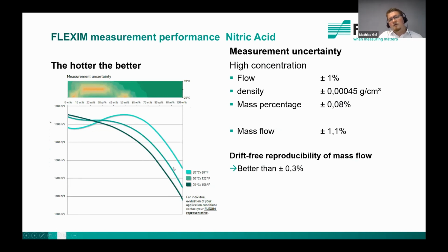And we use this together with a temperature measurement, which can also be done clamp on, or we can integrate the temperature measure you have on site. And then we can calculate the concentration, the density, the mass flow, the mole weight, whatever is required on your end. And for those of you who have asked questions about how accurate this can be, if we're talking about flow, we're always around ±1% in volumetric flow here. And then when it comes to the density measurement, it really depends on the substance. High concentration nitric acid, so starting at 60%, that can be measured really, really accurately here.